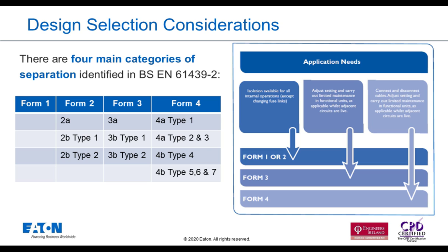So in terms of design selection, there are four main categories in the current standard. You've got Form 1, 2, 3, and 4. There are some subcategories known as 2A, 3A, and 4A, and so on. And then there are the derivatives, Type 1 up to Type 7. I'd like to say that the derivatives are specific to the BS standard. In the IEC standard, we only have the main categories and the subcategories, and obviously in the BS we have the derivatives, the Type 1s, 2s, and 3s.